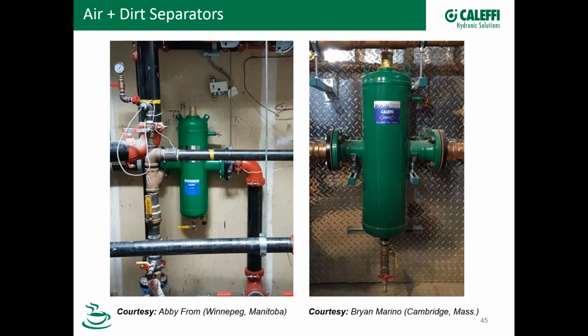Yeah, I got a couple thoughts. Since it looks like we have a little bit of time here, one thing I was thinking about: if you're doing a brand new system with all brand new copper pipe, maybe PEX tubing, a brand new boiler and brand new pumps, I think the more critical application is to get the air at the hottest point in the system, which would obviously be the supply right out of the boiler. Now keep in mind, if a boiler's running at a 20 or 15 degree delta T, you don't have a huge temperature difference between your supply and return.